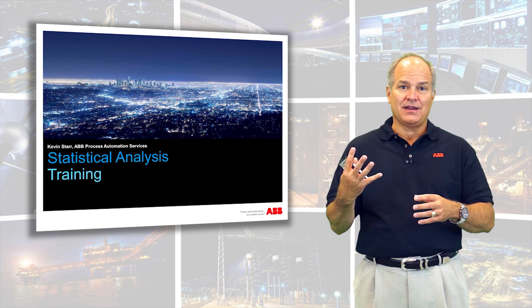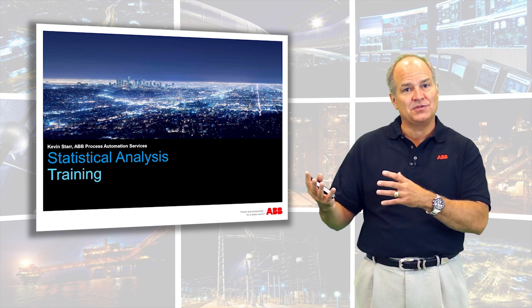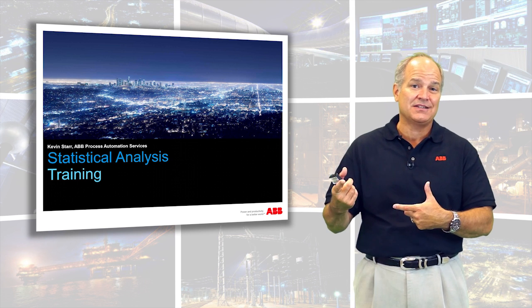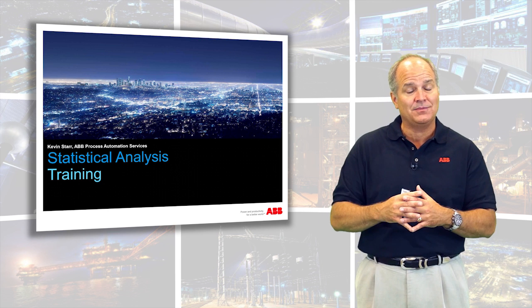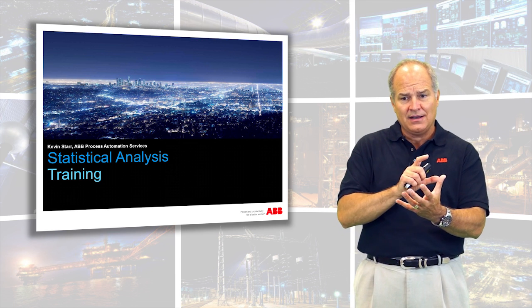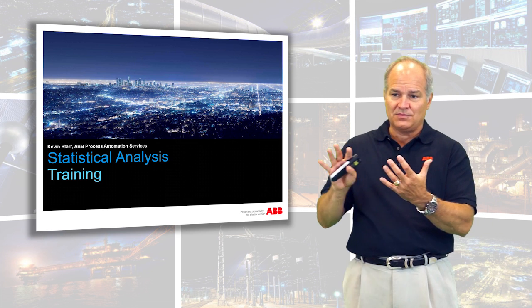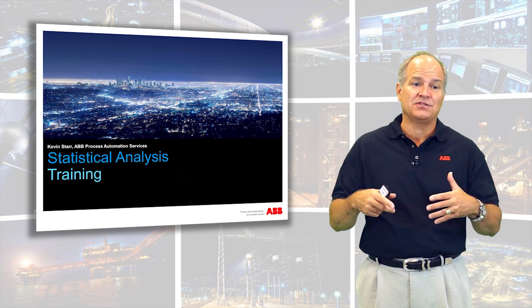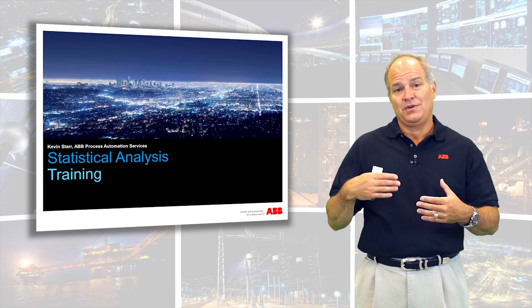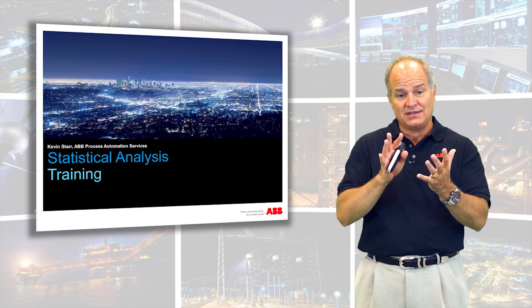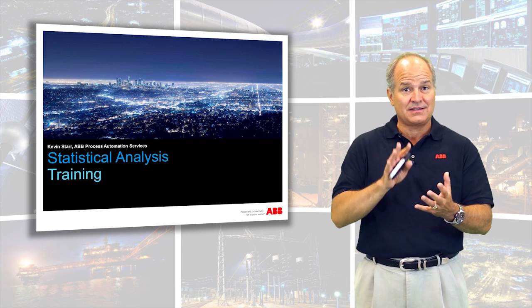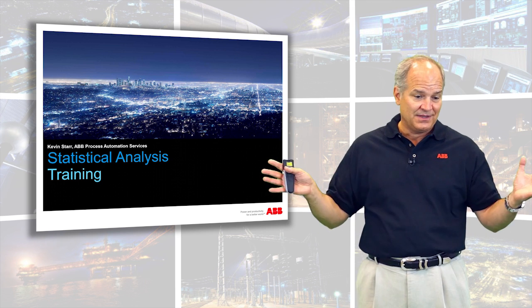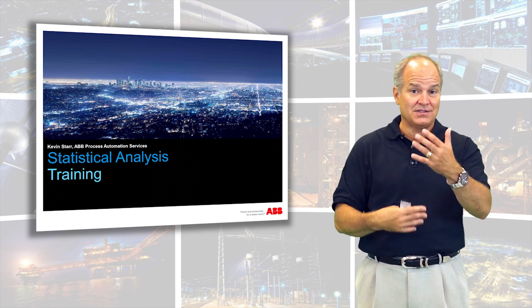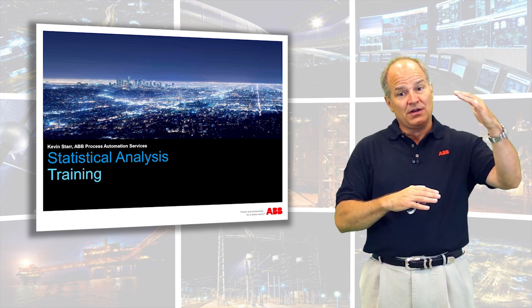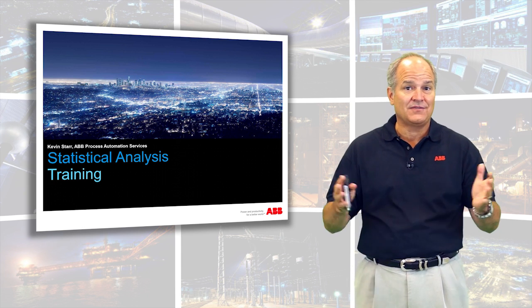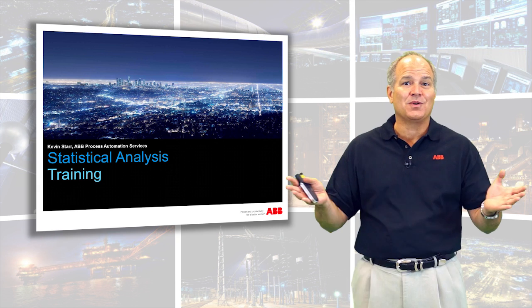Then we looked at a histogram and said, I can actually measure my distribution and then compare it. So now we can start using histograms to measure the bins and the bin width. Then we realized we could look at autocorrelation, to see how a signal changes over time and give us indications of signal to noise, energy. If it had a value of 1, the signal had a high probability of looking like itself after those time shifts. 0 means there's no useful information. A -1 means it's inverted. Our goal in automation is to get within the confidence limits as fast as we can, because that's where noise is. That's white noise.